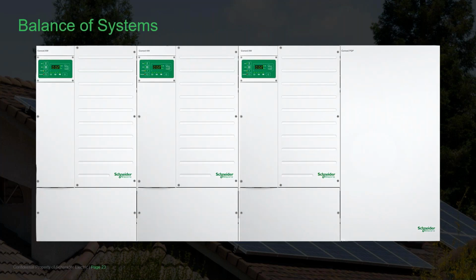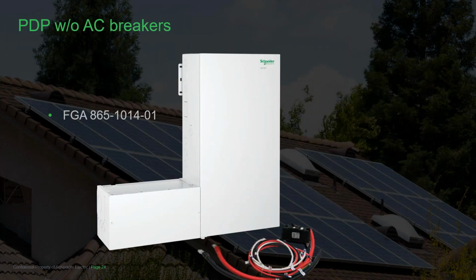Now let's focus on how everything physically connects together. Note the system has zero clearance mounting capability with the power distribution panel to the far right. All knockouts are symmetrical for mounting the power distribution panel on the left or even in the middle if preferred. The power distribution panel without AC breakers is part number 865-1014-01. It is typically the part number that you would use for the three-phase system.